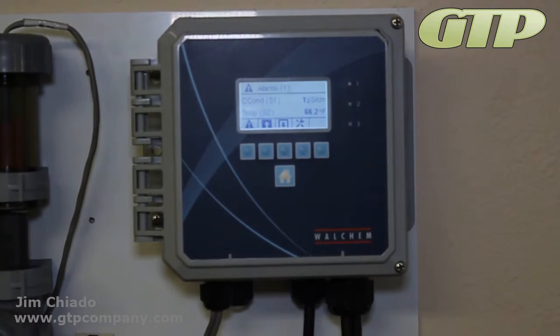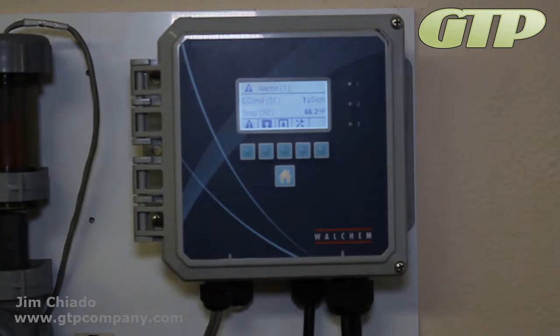We want to talk about setting up a paddle wheel sensor for flow. This machine will understand flow meters and flow sensors, more like the Seametrics or the Signet flow sensor. So we're going to go to inputs. That would be on the input side coming into the machine.